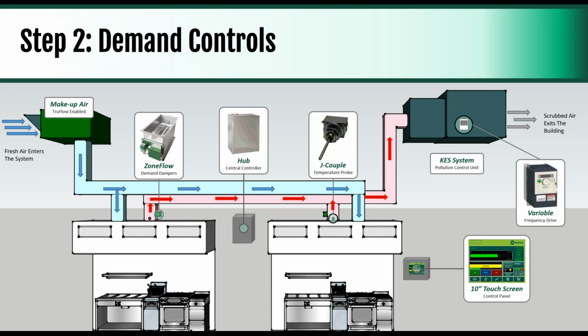And so the components we're adding here are temperature sensors in the duct collar, a central controller, and then demand dampers. So that's our zone flow dampers. It actually allows you to operate, I think we can do up to 16 hoods on one exhaust fan. And if only one set of appliances is cooking, that duct collar is wide open, the rest are closed, and that exhaust fan, or KES in this case, is probably only running at 10%, rather than running at 100% capacity and wasting all that energy, specifically with the makeup air.